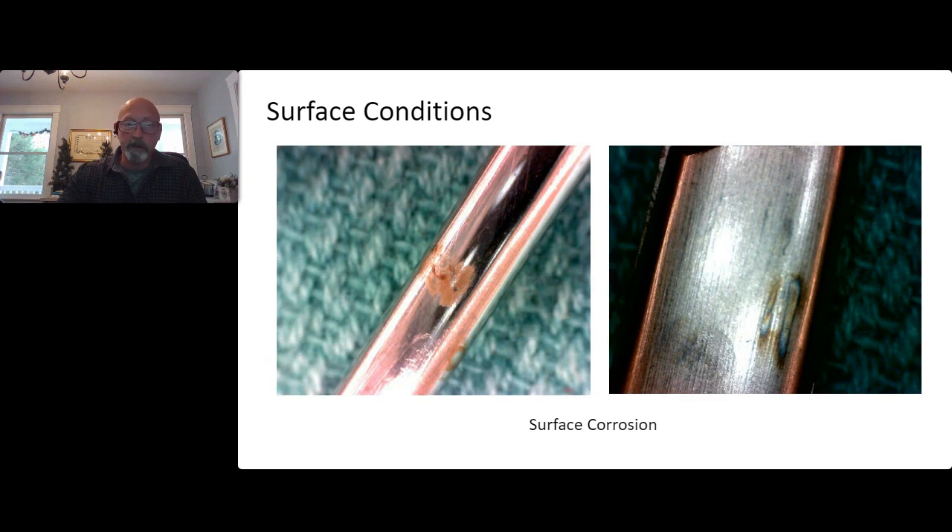Other typical corrosions include an old tape line that could be a pit or bioburden. When you refurbish instruments — wheel marks, sandblasting — you increase surface area and create little grooves, giving you more reservoirs for staining. Without dealing with your root cause first and then refurbishing, you're more likely to see more corrosion going forward. Spend money on fixing the root cause before revamping an inventory.